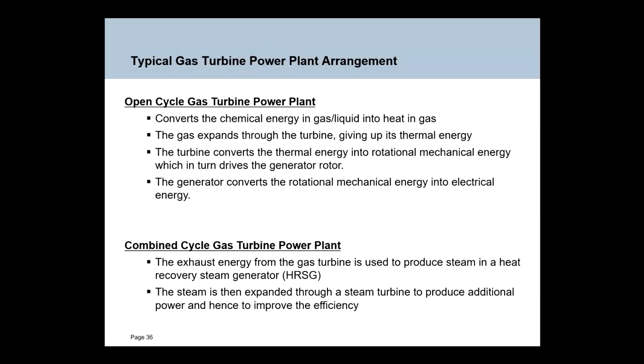Okay, the two types of gas-fired power station. First one is open cycle. So here the exhaust gas from the gas turbine is simply exhausted to atmosphere, typically at around 400 or 500 degrees C. So you're actually losing quite a lot of heat to atmosphere in an open cycle gas turbine plant. In a combined cycle plant, you exhaust the gas from the gas turbine into a boiler, typically known as a HRSG, a heat recovery steam generator. And that boiler produces steam, which is then expanded through a steam turbine. And you'll get a much higher efficiency out of that combined cycle unit.